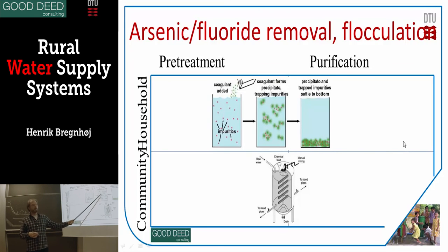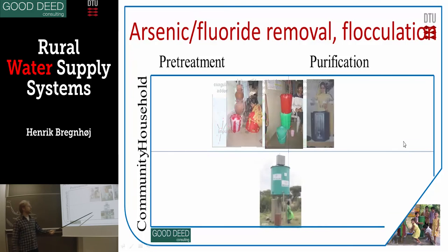where the aluminium will form aluminium hydroxide, and it will form some flocks, some kind of precipitate, and that precipitate will grab the arsenic or grab the fluoride, and then it will precipitate to the bottom here. That is the principle in both the household version and in the village plant here. You can see here you add the coagulant, you may need to add some base also to change the pH, but in some cases you do the same in here.